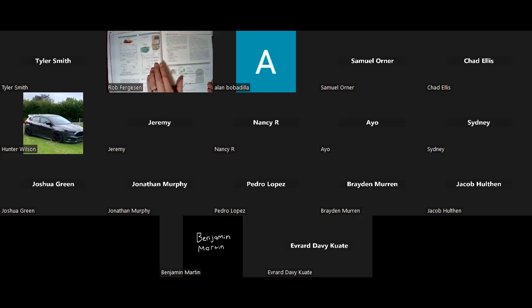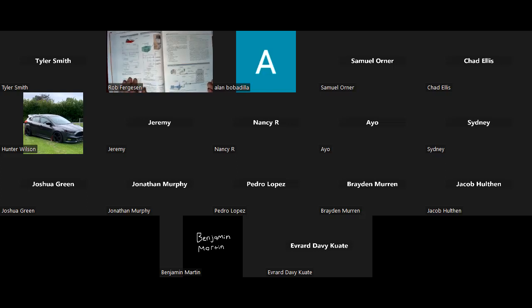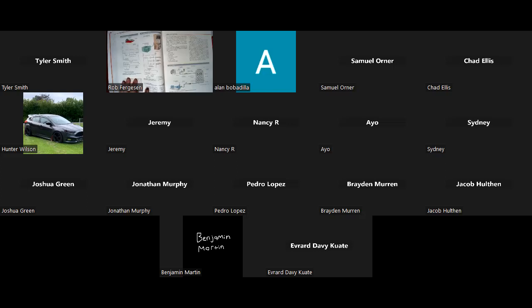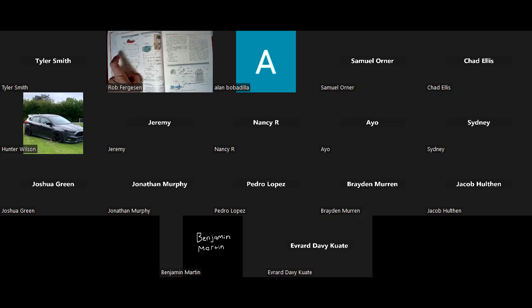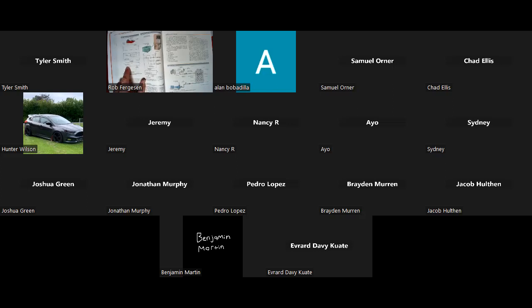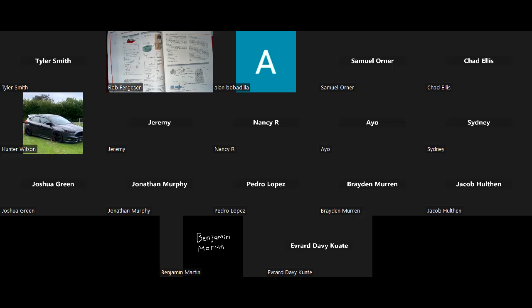And we give you various applications here. In this case, we've got a heating system with a very simple temperature switch. All right. In this case, we show a heating system being controlled by a contactor. That C means a contactor. And that contactor is being controlled by a temperature switch, which is a normally closed. They show it as a normally closed switch. And basically temperature switch is just a switch with a line going down and then this little square squiggle. Square squiggle is a temperature switch. All right. When the temperature reaches a certain point, it opens. When it closes, that means the temperature is cooled to a certain point. You can buy these normally open or normally closed.